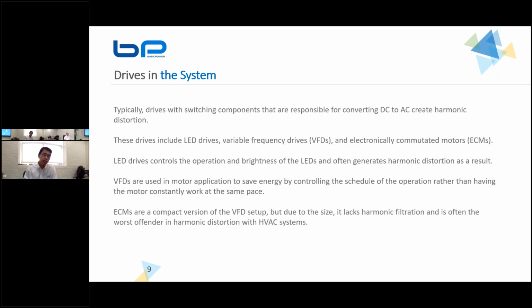Now, typically the drive itself is called a variable frequency drive. LEDs also have these drives, or ECMs, which are electronically commutated motors. All of these have a conversion from DC to AC. When these drives do these conversions, that switching in itself causes harmonic distortion. In any new system with new LED systems, VFDs or ECMs, you'll typically see a lot of harmonic distortion. And when you measure the waveform, you can actually see the 6-pulse waveform, which is that humpback you saw in the motor previously.